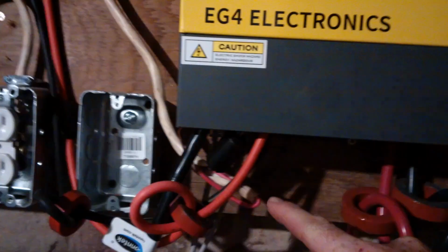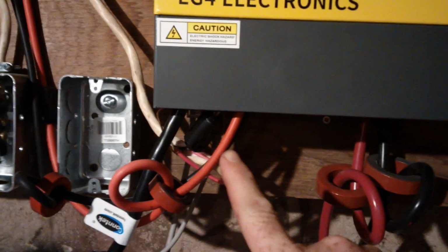So this is my USB 3 to serial DB9, and then it connects up to, this is an EG4 unit with the RJ45 network, basically Cat5 connector on the bottom there. So what was happening, this was showing all green, all lights solid, red, yellow, and green, and it wouldn't start, and so it showed "unable to set remote address." And it seems to like that particular USB top right plug for some reason.